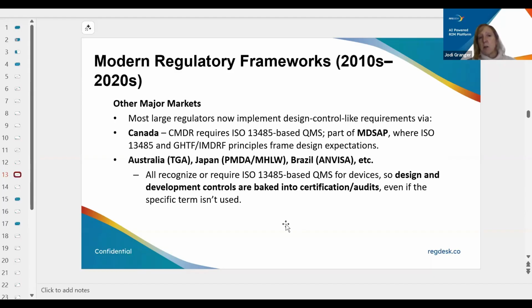Other major markets have similar frameworks. As I mentioned, most large regulators now implement some kind of design control requirements. Canada has a CMDR. It requires an ISO 13485-based QMS. The MDSAP program is a requirement in Canada: you need an MDSAP certification in order to register your products. Australia, Japan, Brazil, all major markets really are putting similar frameworks in place. All of these will be audited as you submit your registrations. If you don't have certificates in place that each country accepts, each of the organizations can audit you independently as well.